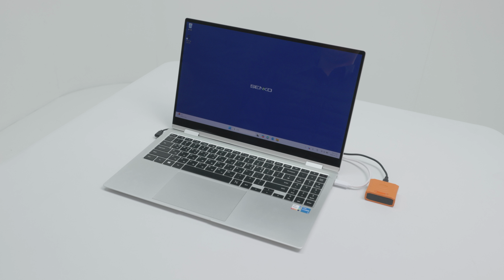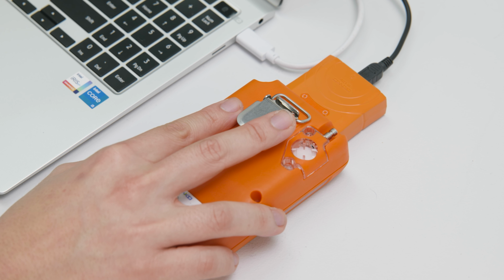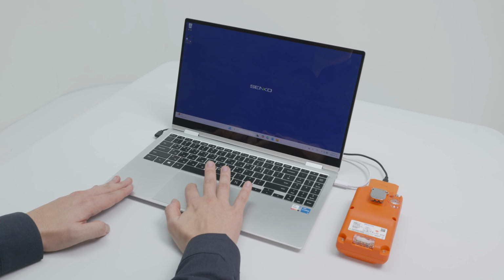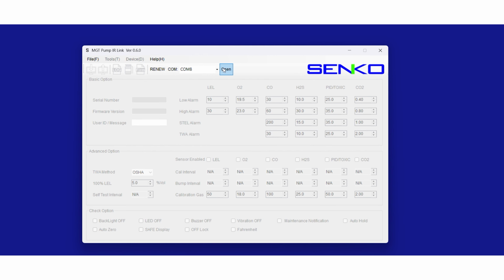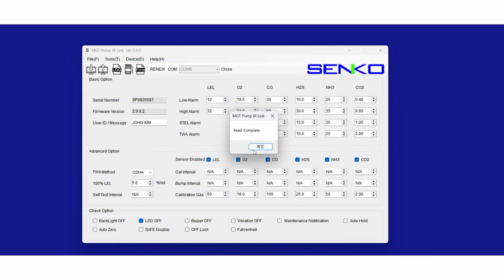The IRLINK is an accessory that allows the SP-MGTP to be connected to a PC for advanced configuration and maintenance. Now let's take a look at the IRLINK software and how it works with the SP-MGTP. To use the IRLINK, first connect it to your PC using a USB cable and run the IRLINK software. Then, align the IRLINK with the IR port on the top of the SP-MGTP. Once aligned, the device will connect automatically and the device information will appear on the screen. After the connection is established, you can start managing the device through the software.